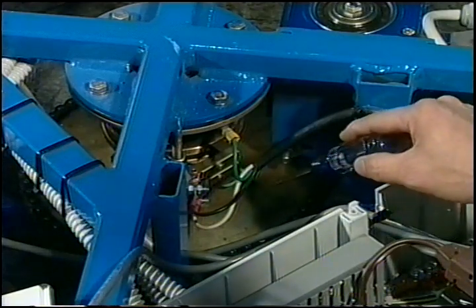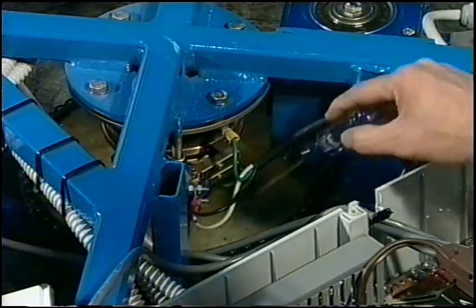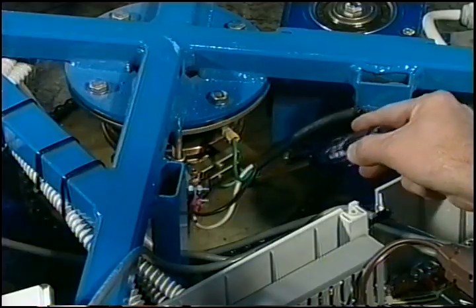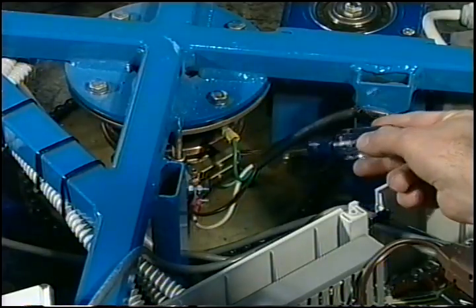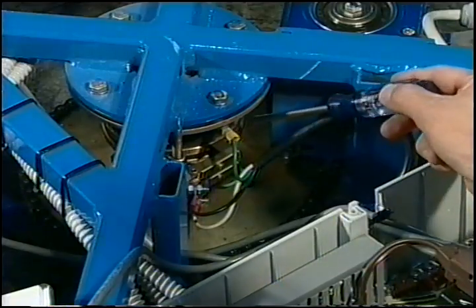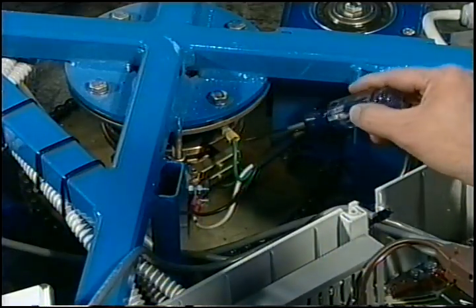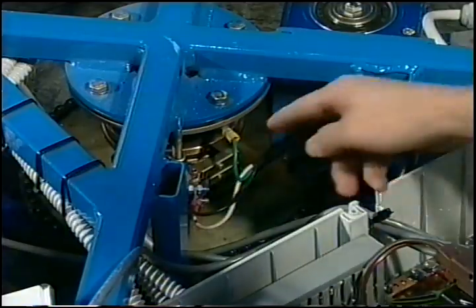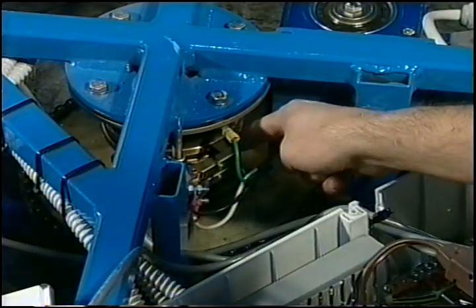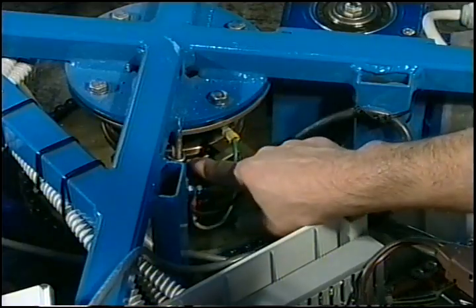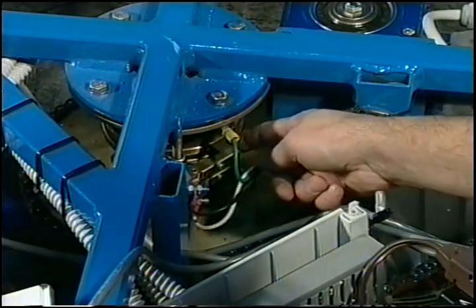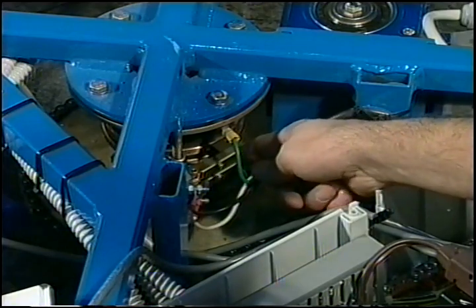Your main power from your power cord comes in through the rotation wheel right here. You have your hot and your neutral. It comes up through the center of the slip ring assembly. Your top wheel is your hot, your bottom wheel is your neutral. And then you have these brushes that are constantly pressing against it because of the springs. This is your top brush, and this is your bottom brush.